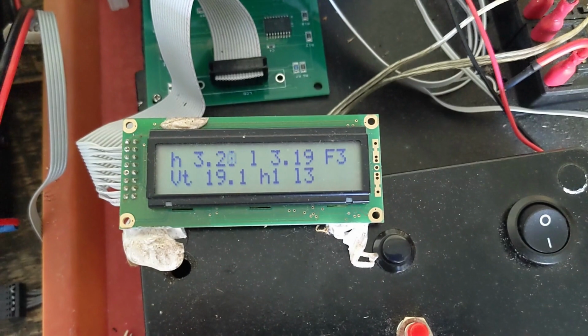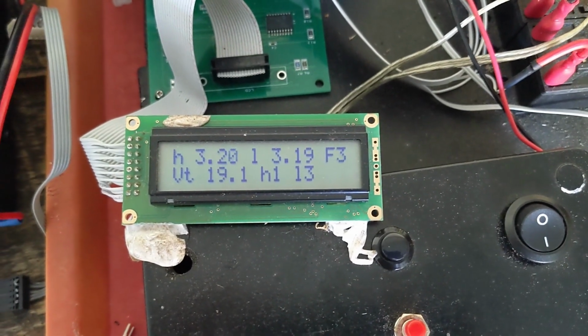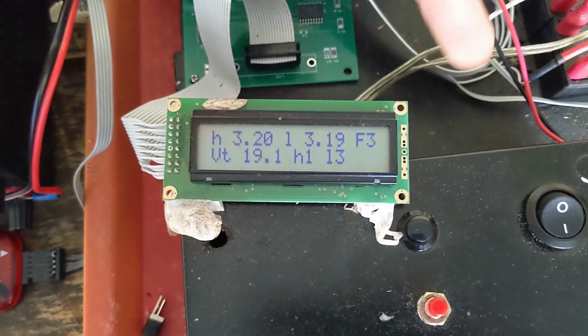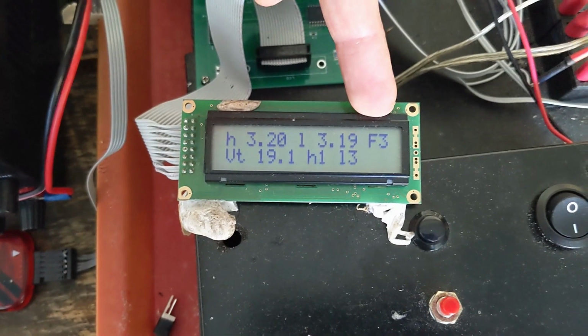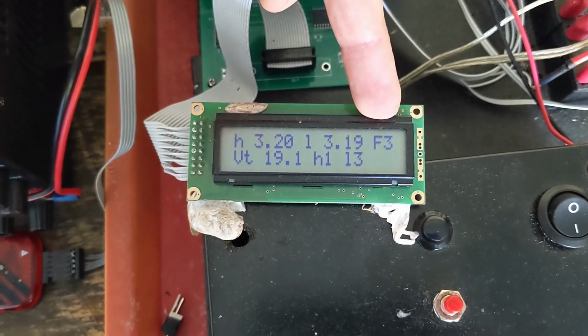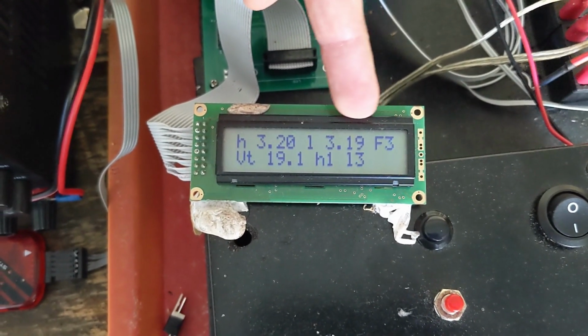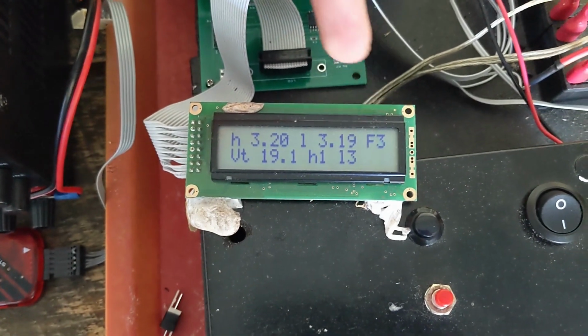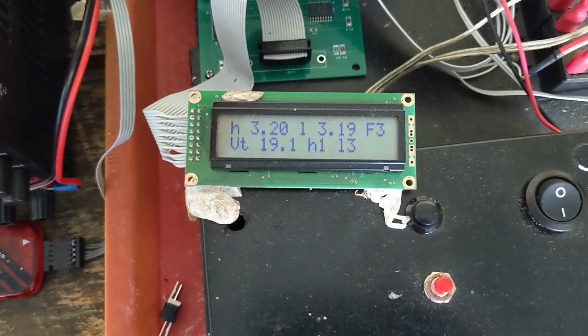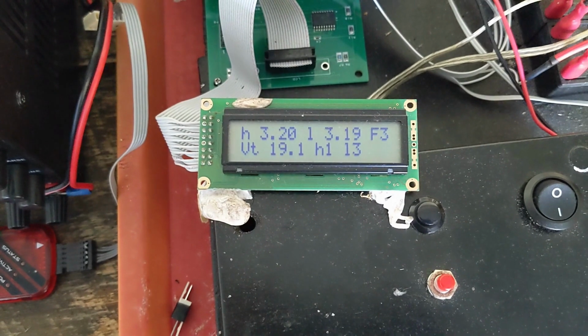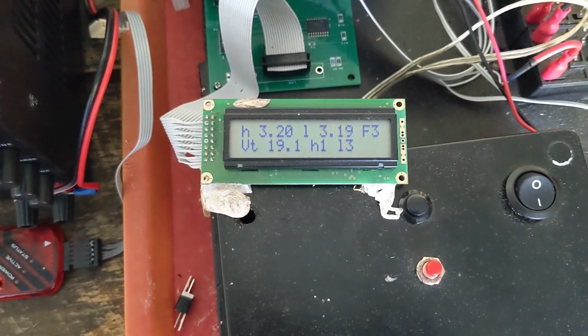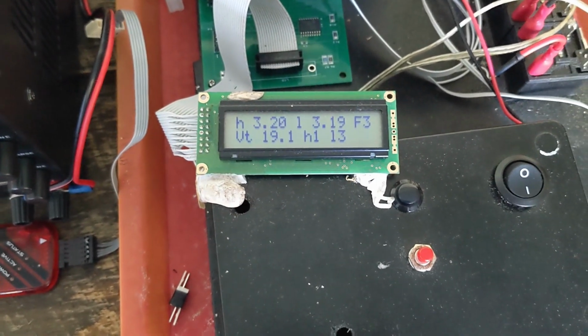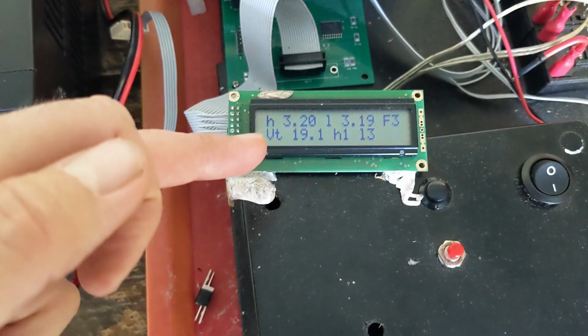We're getting pretty close now. We're down to 3.19. We've got F3, that's fault 3. That means that we're getting low voltage, low cell voltage, so 3.19 is below the threshold. But we're not yet to the state where we're going to turn off the relay. So you notice the total voltage, 19.1 volts.